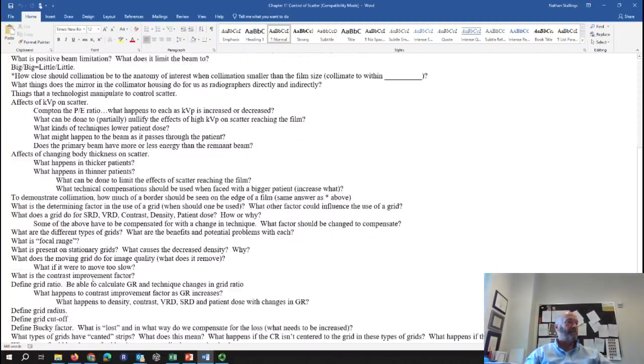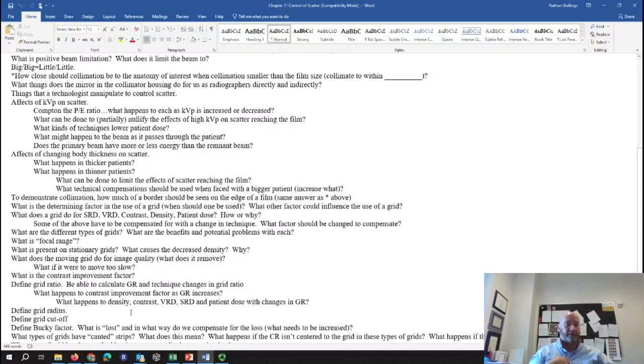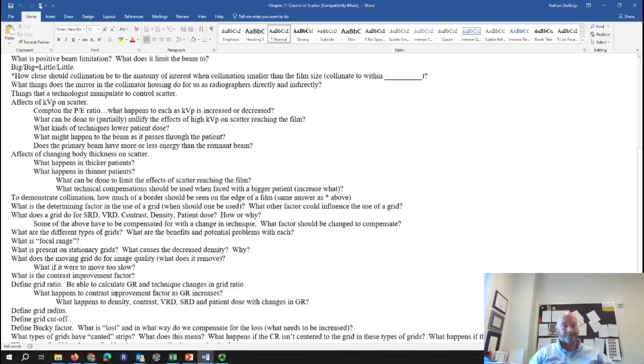The contrast improvement factor — also called the K-factor — is basically how effective the grid is: a comparison of contrast with a grid versus without a grid. Higher grid ratios have better scatter cleanup, a higher contrast improvement factor, and are more efficient. As grid ratio increases, the contrast improvement factor increases.